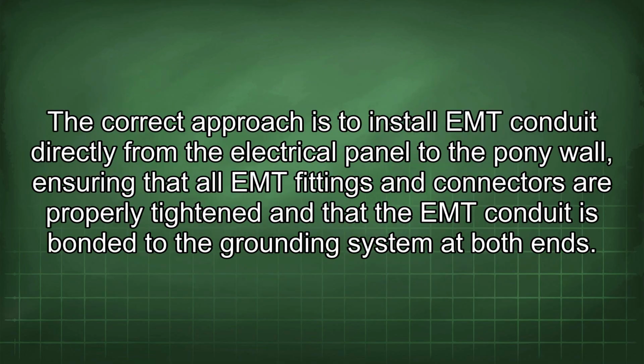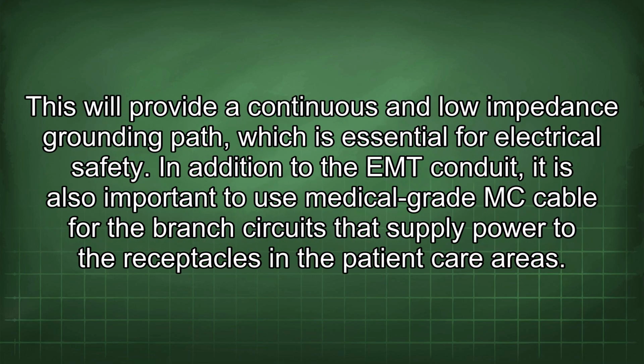The correct approach is to install EMT conduit directly from the electrical panel to the pony wall, ensuring that all EMT fittings and connectors are properly tightened and that the EMT conduit is bonded to the grounding system at both ends. This will provide a continuous and low impedance grounding path, which is essential for electrical safety.